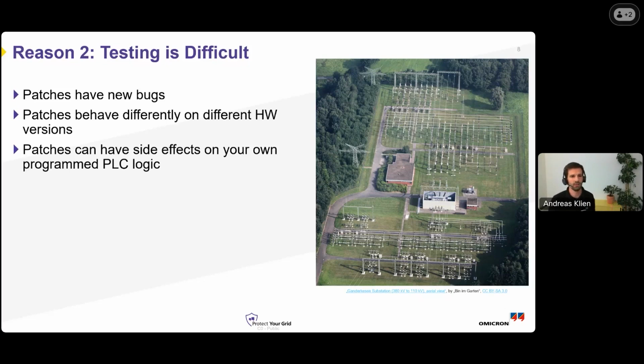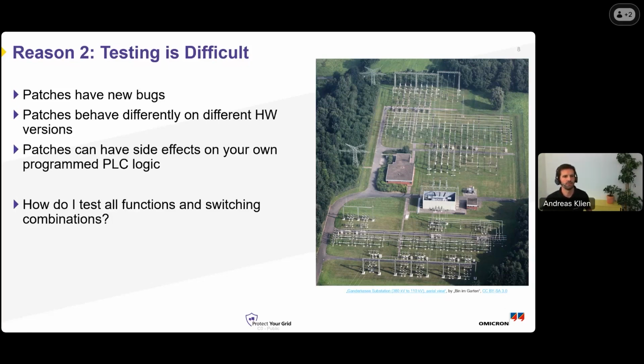So even if you test your patch in a lab environment, it's not clear it will operate the same way in the actual substation. How do you test all these functions and switching combinations? In reality, it's a bit sad that in many cases these logic combinations can only be tested by executing them, by really switching the breakers in the yard of the substation. Obviously this cannot be done, since we're again talking about de-energizing power lines, which is not possible.